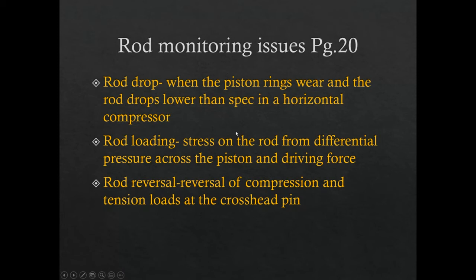So most of the time, issues are going to be related to pressure, temperature, vibration, loss of lubrication, and the physical things that come along with that. Once we lose lube oil, for example, temperatures are going to start to rise. Things are going to start wearing out. Pressures are going to start dropping because the rings are going to wear out and things like that. So they're very associated together. So a lot of things that we need to look at.